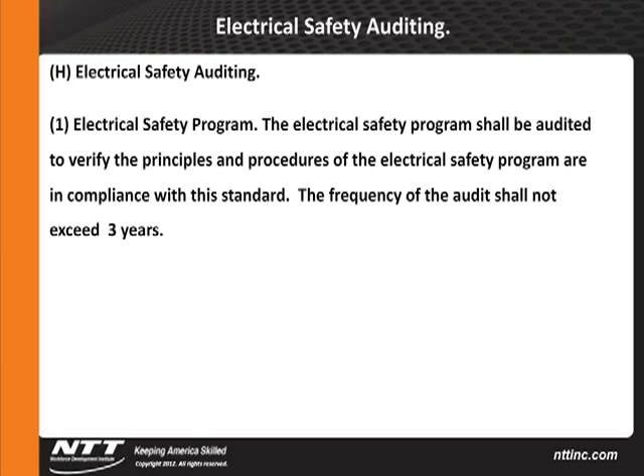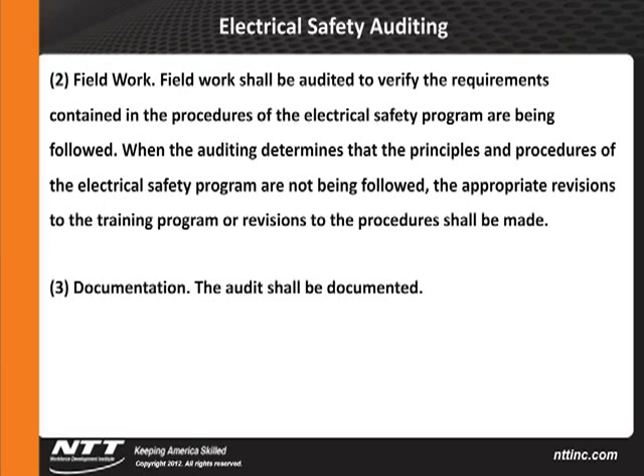Field work, another new section. Field work should be audited to verify the requirements contained in the procedures of electrical safety programs are being followed. Why is that important? Because many of us send people out in the field, not at our location, to be a contractor. We need to go out and see what they're doing. When the auditing determines that the principles and procedures of the electrical safety program are not being followed, the appropriate revisions to the training program and revisions to the procedures shall be made. And again, documentation. The audit shall be documented.